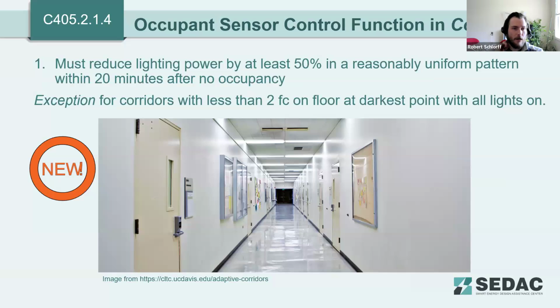All right, so occupant sensor control within corridors. This is a new section, as I said earlier. Controls within corridors, occupant sensing controls must reduce lighting power by at least 50% in a reasonably uniform pattern within 20 minutes after no occupancy. There is an exception listed for corridors with less than 2-foot candles of lighting on the floor at the darkest point with all lighting on.